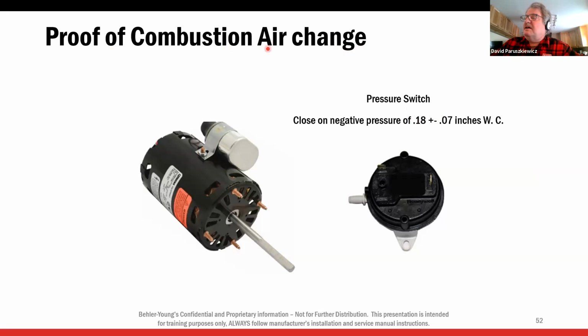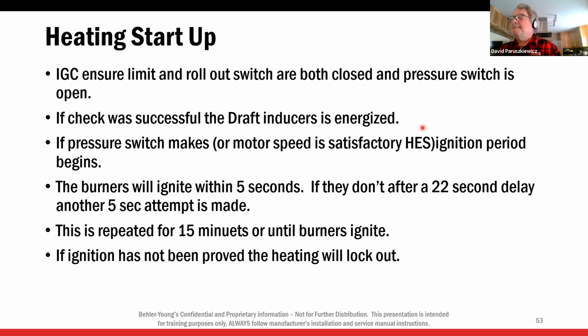Proof of combustion. For years, we used what was called a Hall effect sensor for our inducer. So the inducer came on, we had a Hall effect sensor. Several years ago, we went back to a pressure switch. So the inducer is always going to be the first thing to come on, even on most furnaces. Thermostat calls, inducer comes on. All right. Then we have a pressure switch. We'll talk about the Hall effect sensor because we did use a lot of them as we move on here. So on a call for heat, first thing comes on the inducer, pressure switch makes 0.18 is when it's going to close, the negative 0.18. Okay, that sends a signal to the IGC.